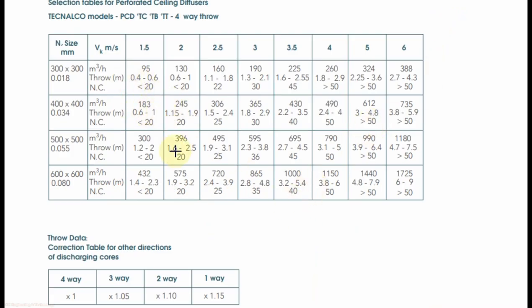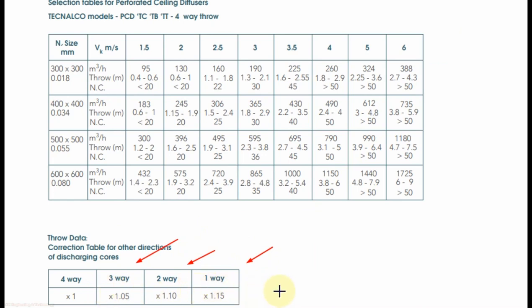The throw data in this table is for the 4-way type. If you need to select for 3-way, 2-way, or 1-way type, you need to multiply the throw by a correction factor. For 3-way type, multiply by 1.05. For 2-way type, multiply the throw by 1.1. For 1-way type, multiply the throw by 1.15.